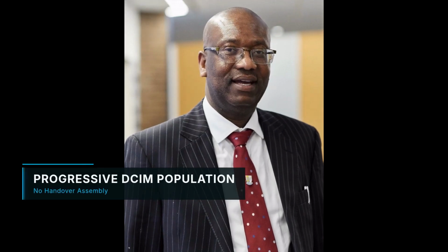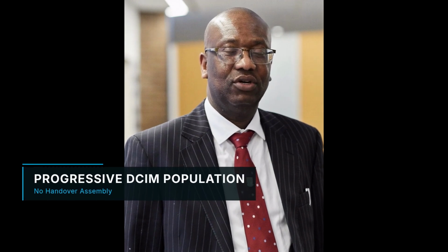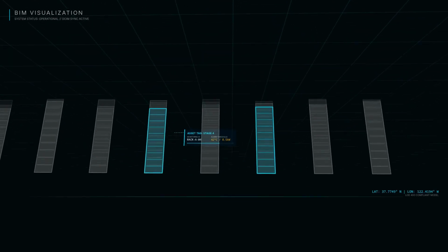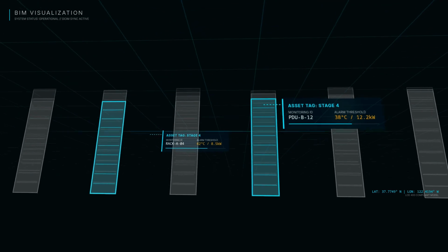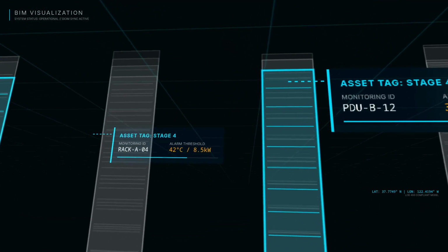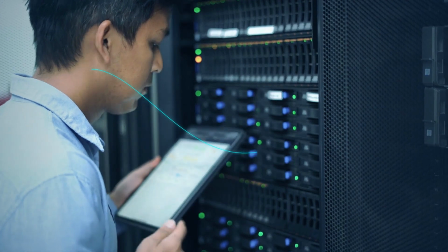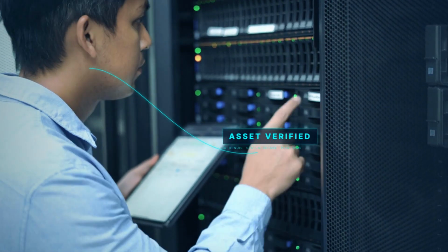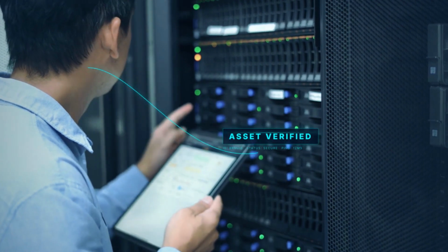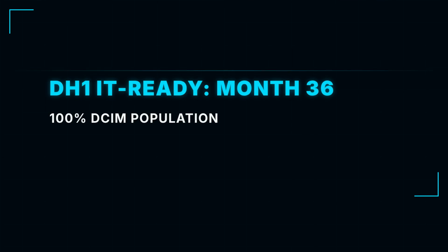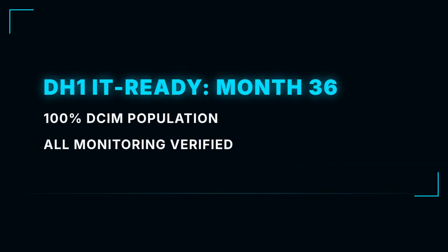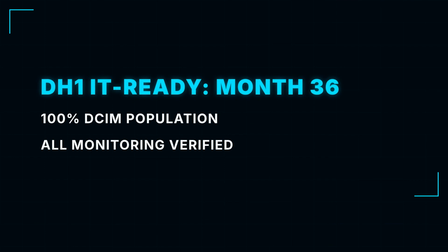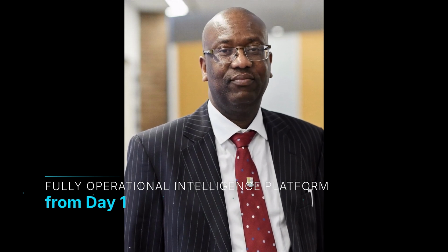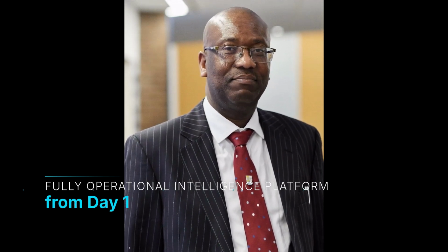Crucially, FULCRUM's DCIM is populated progressively through construction, not in the final week before handover. Every physical element is tagged in the BIM model at stage 4 with its DCIM ID, monitoring parameters and alarm thresholds. When equipment is installed, the site team scans its QR code to confirm, automatically linking the physical asset to its digital record. By the time DH1 reaches IT ready at month 36, the asset register is 100% populated and verified. The team receives a fully operational intelligence platform from day one, not a skeleton system they must build themselves.